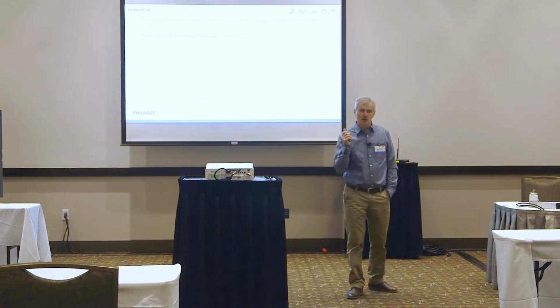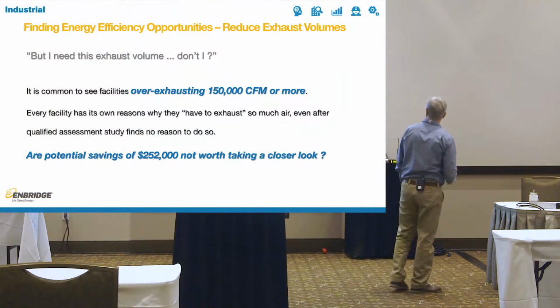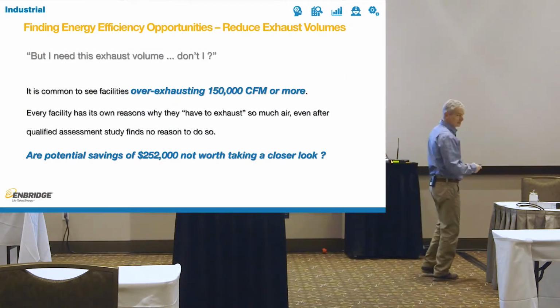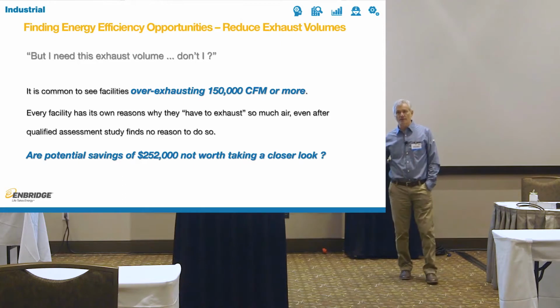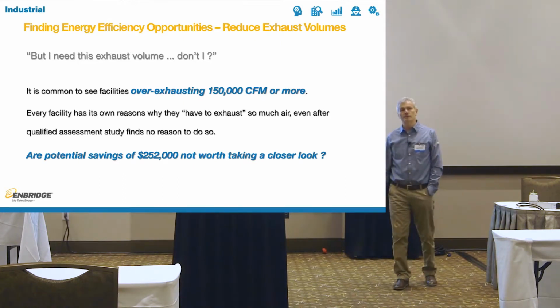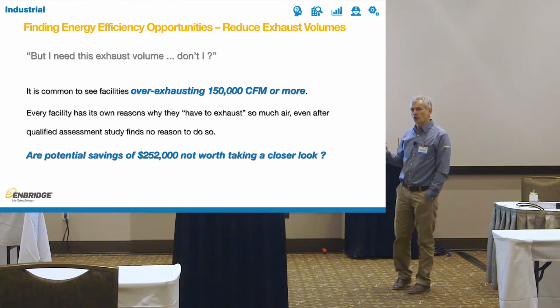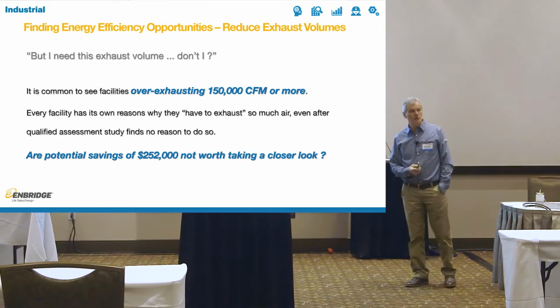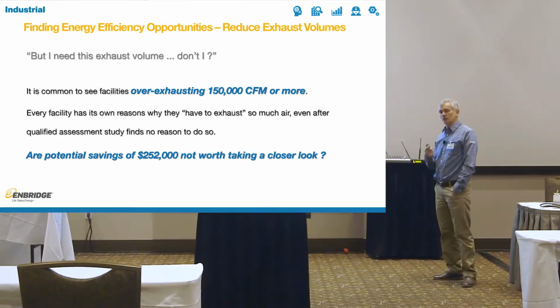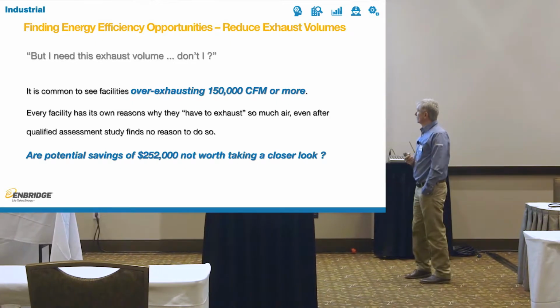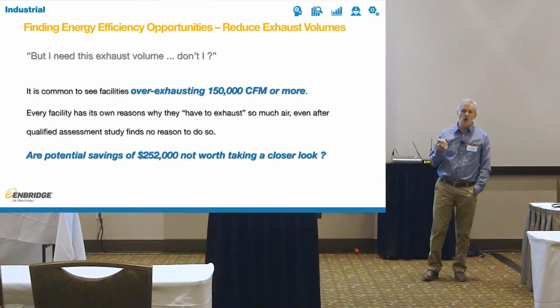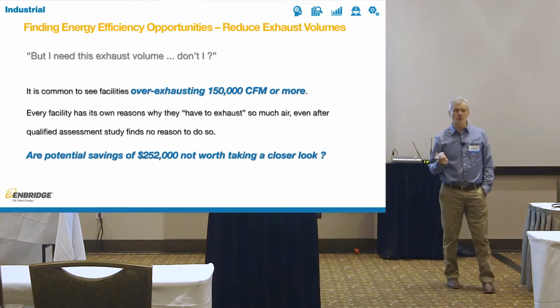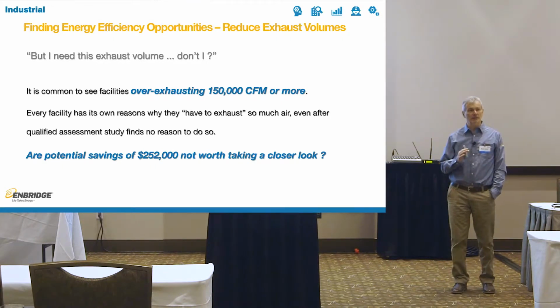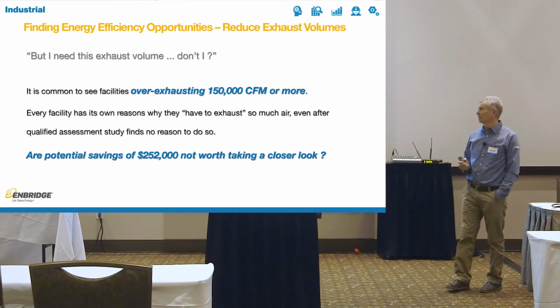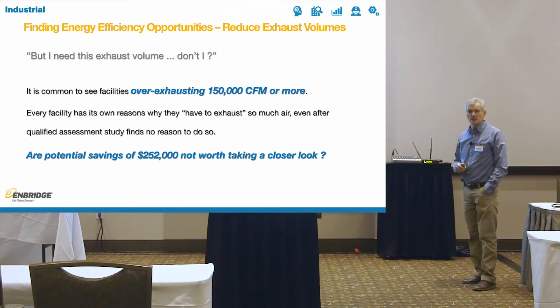So now that we've seen the example of what additional exhaust can do, the question is always this. And this keeps coming up in one form or another. But I need all that exhaust. I can't help it. That always is a question. It always comes up. It's always an excuse for doing nothing or just adding makeup air because it's that simple a solution. So what we see is it's very common to exhaust 150,000 CFM or more. That's a very common thing in Southern Ontario. It happens all the time. I'm never surprised when I see 150,000.